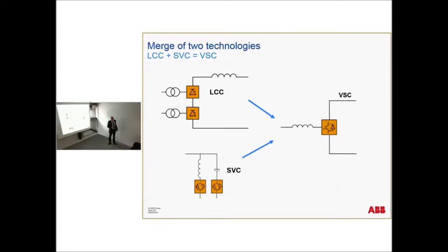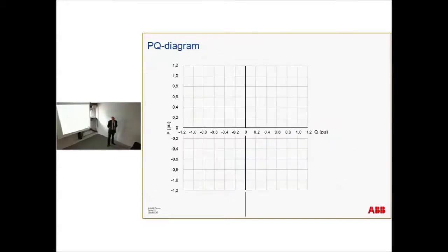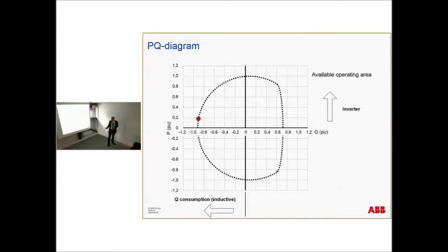If we look at the function here, when you buy and install an HVDC light, you will not only get the AC to DC conversion, you will get an SVC or a STATCOM. At the same time, it's inherent. So if you combine the LCC concept with the SVC, you get the VSC functionality. And that means that we can work in all four quadrants of a power and reactive power diagram here.